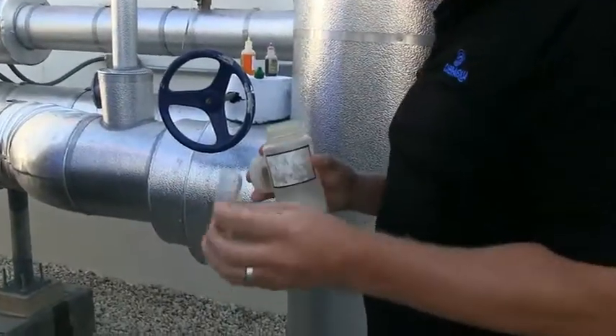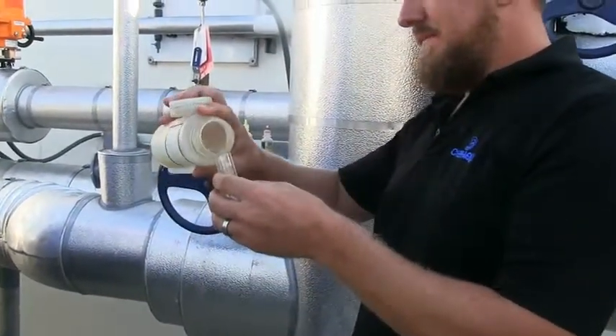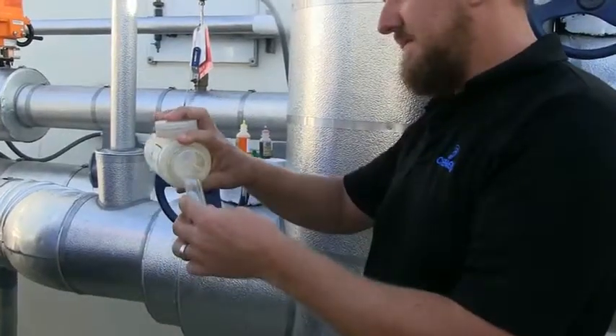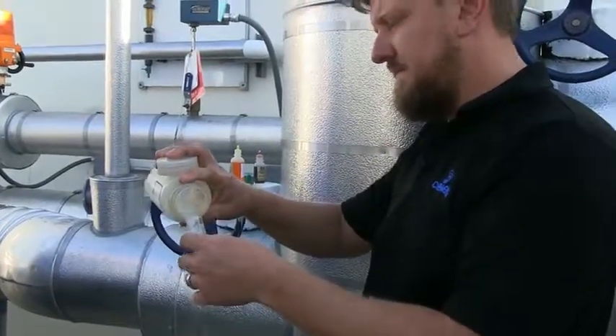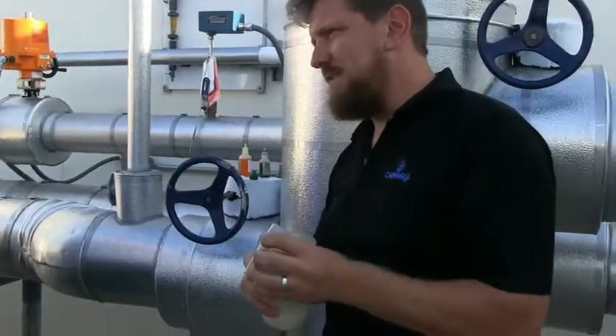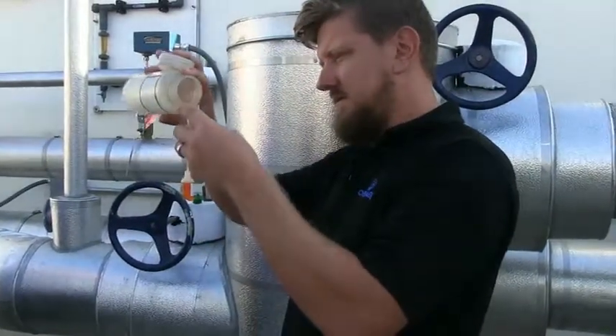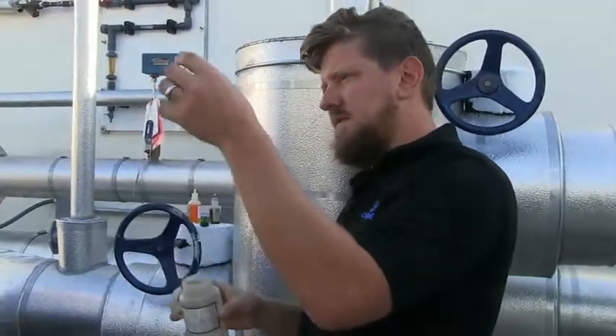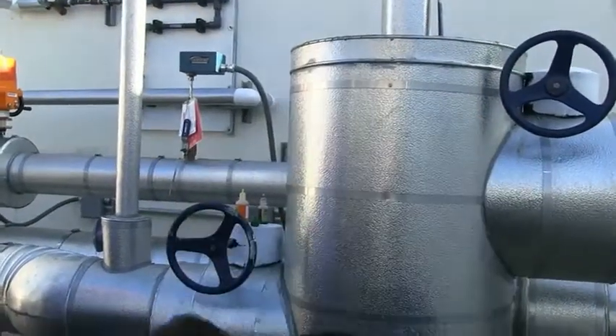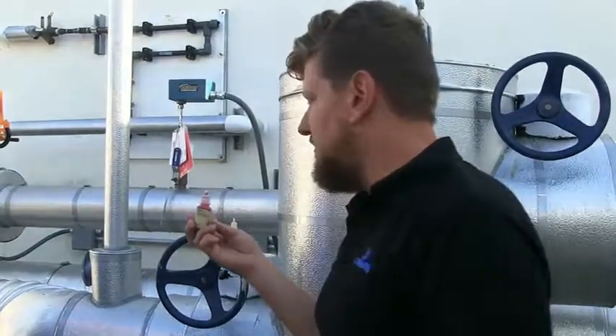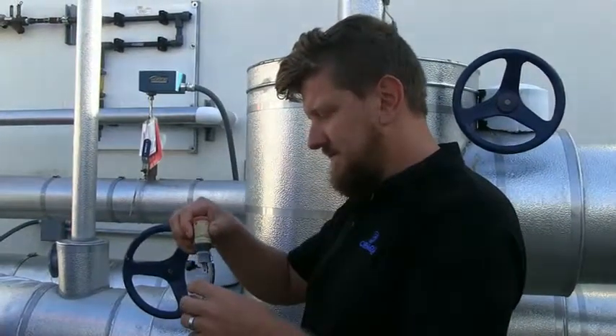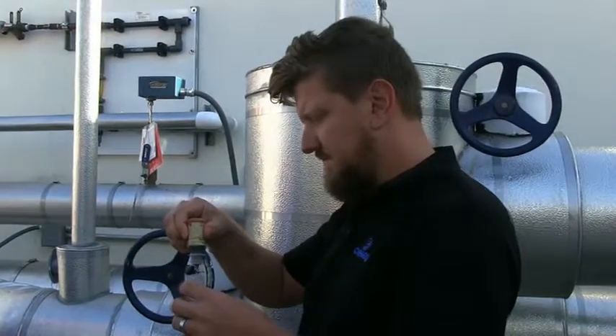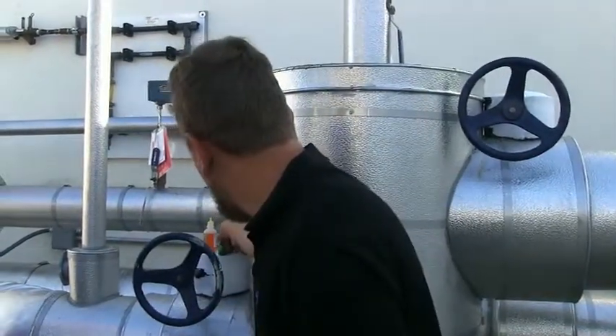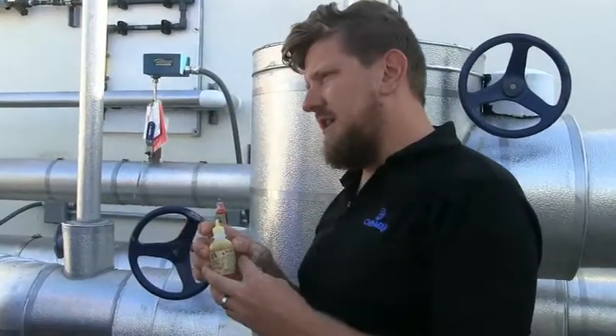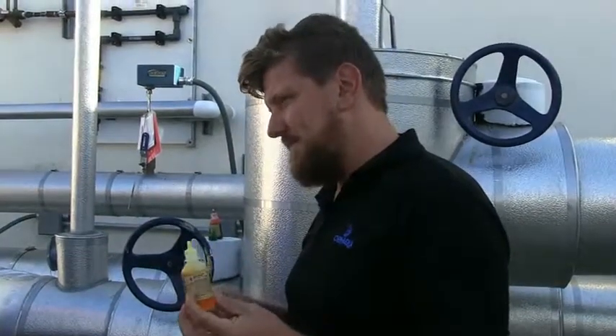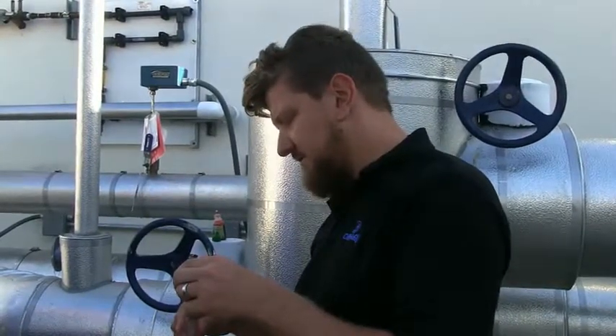You're going to take your sample vial. You'll have 2 tests. Rinse it 3 times. Then you're going to look for the 5 mil line. Fill it right up to the 5 mil line. You put 4 drops of your indicator. And then your solution here, each drop is worth 40 ppm. So you'll count as you go.